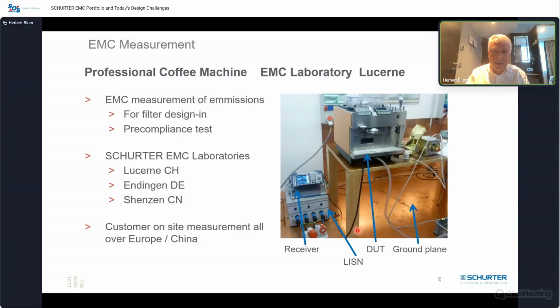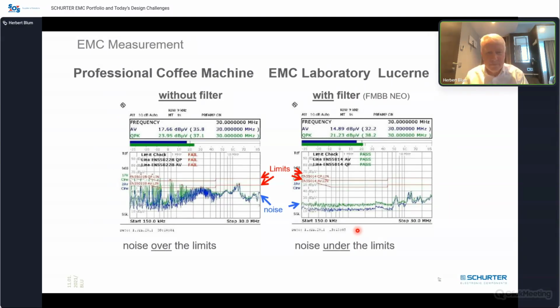As an example, this could look like this graph here. On the left side is the noise over the frequency range from 150 kilohertz up to 30 megahertz, over the limits, as you can see here or here. These are the limits, according to the standards. This is the 55022 standard, class B, or with filter, the noise level should be much lower.